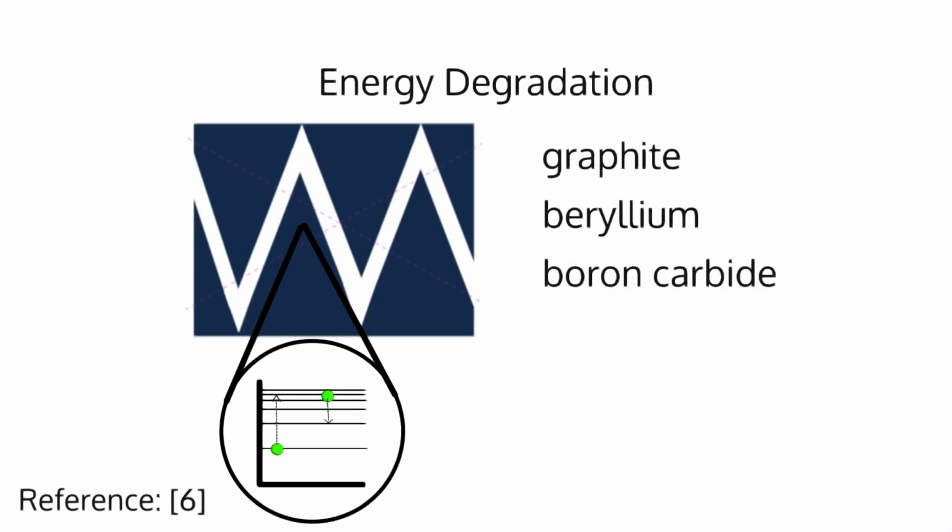However, due to the inherently statistical nature of quantum processes and interactions, the amount of energy the proton loses can vary greatly. This can be due to the number of interactions the proton has in the medium, or the amount of energy the proton transfers to the electrons when interacting. For example, a proton exciting an electron would lose less energy than one that purely ionizes it. This results in a large interval of energy for which the protons are in, and as such must be passed through an energy selection process.